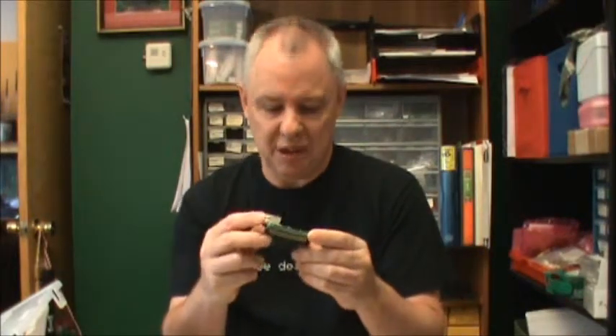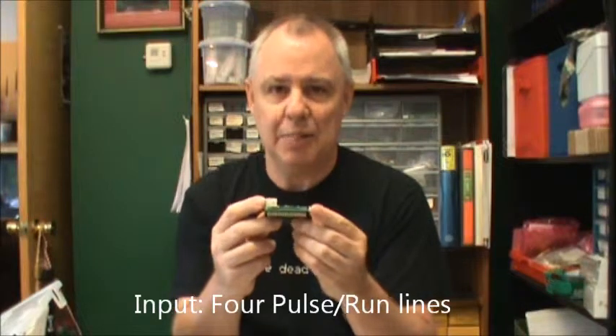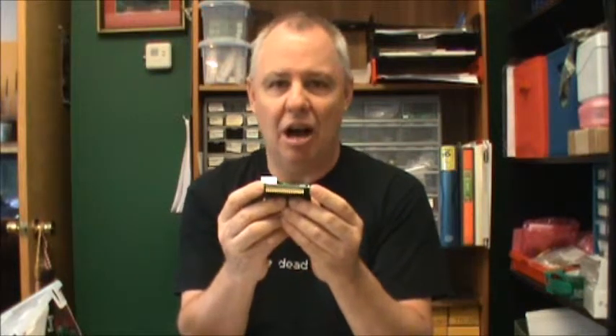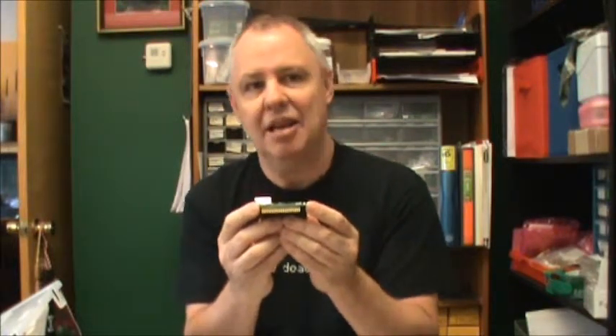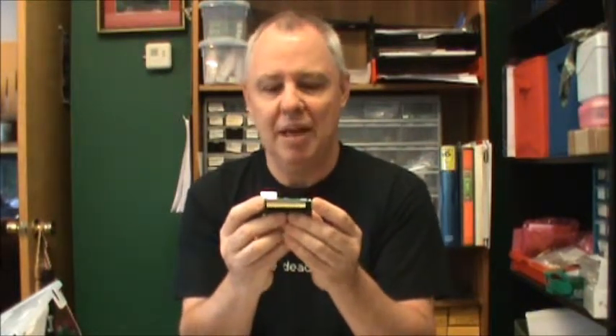The Ultra also has four run pulse inputs. That's basically a digital input designed to hook up to a contact closure or open collector output. It can act as either a pulse counter or a run input. The software does both simultaneously, so you can count how many times the pump turns on, monitor how long it's on, and whether it's on at the moment.